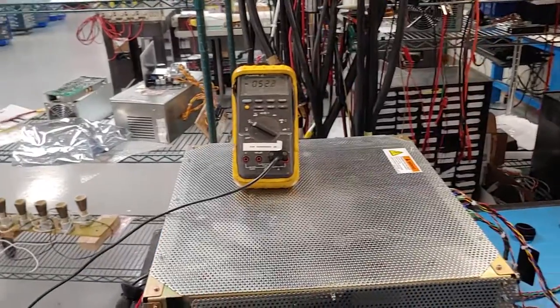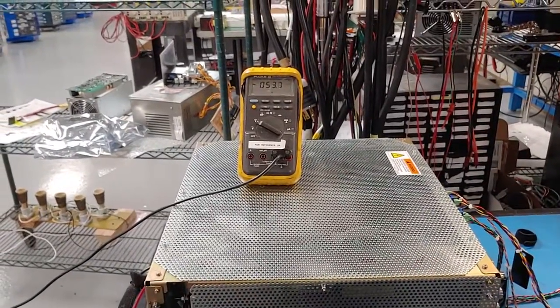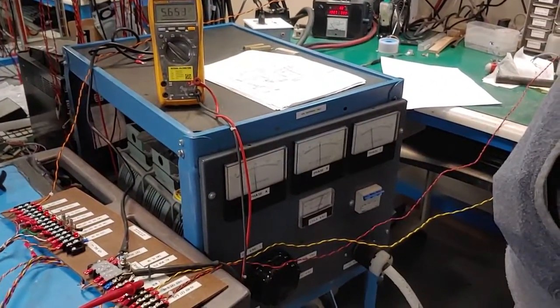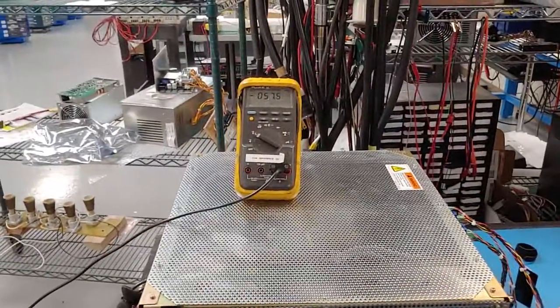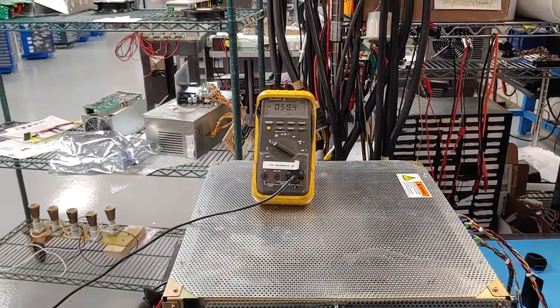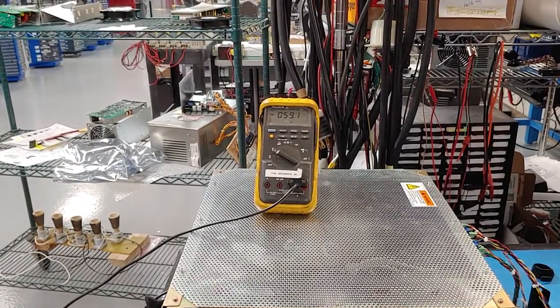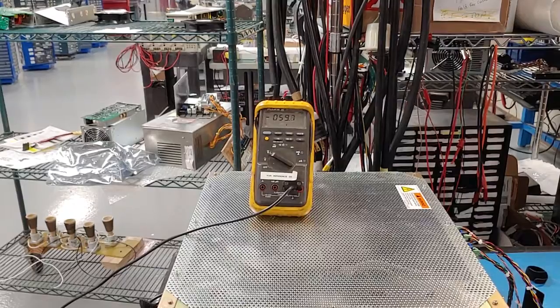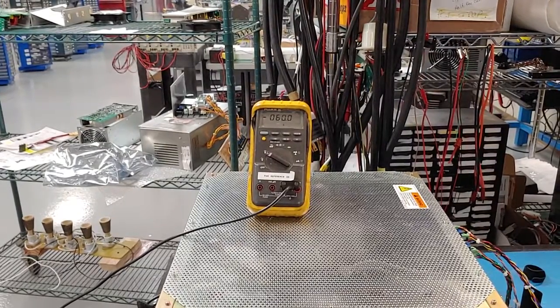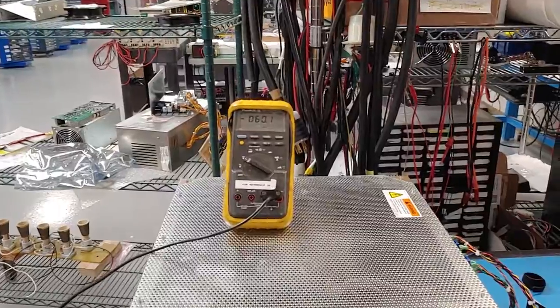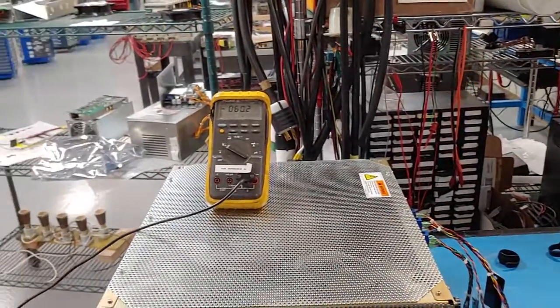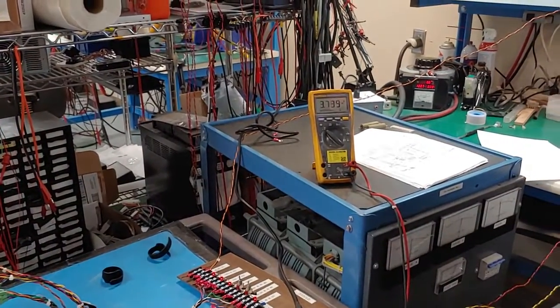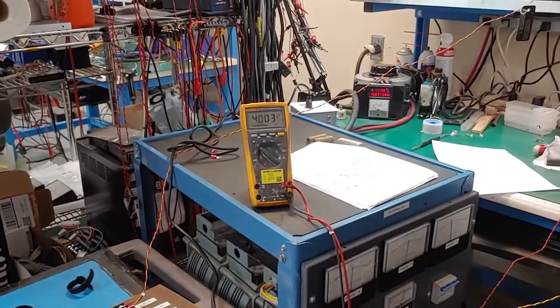We're going to start really pulling some AC current now. We're going to get up to about 9 or 9.5 amps AC, putting in this thing at 200 volts. There's 57,000. Okay, coming up close to our maximum. There's our maximum. There's 60,000, and my current at 60,000 into 1.5 million ohms over there should be 40 milliamps. And if I check this, I'm running 40 milliamps right now, so I am 100% loaded on the high voltage completely.